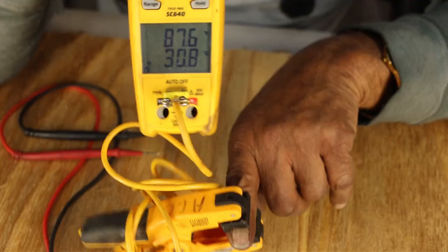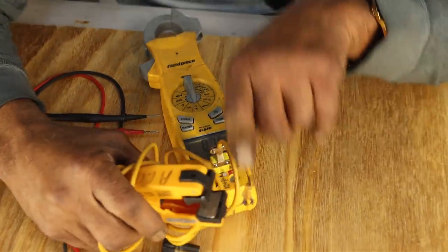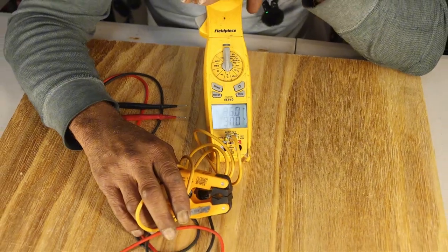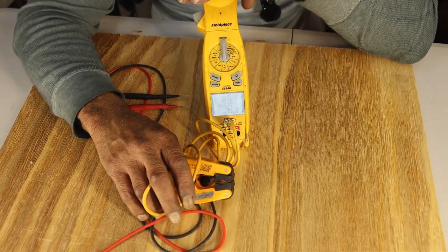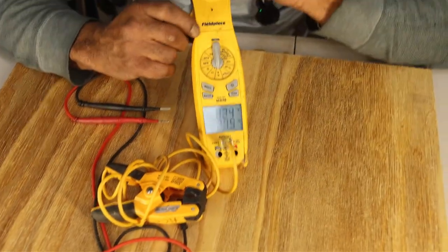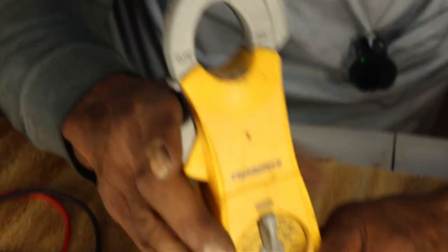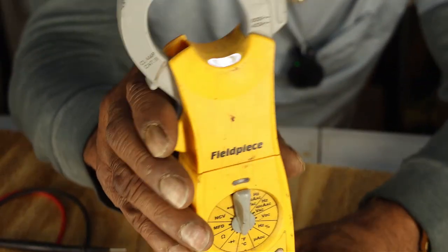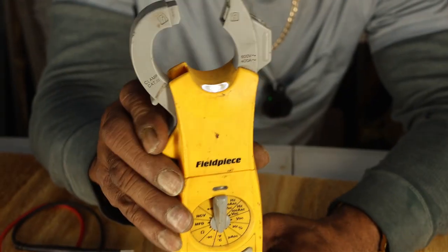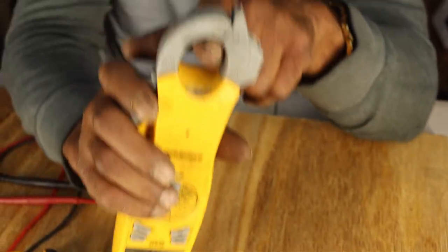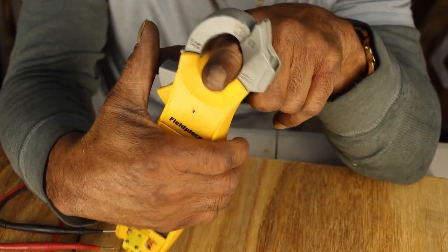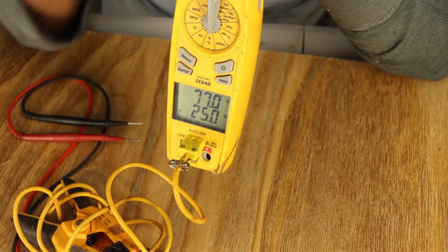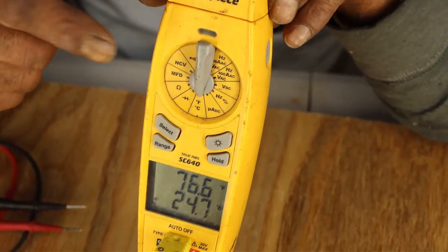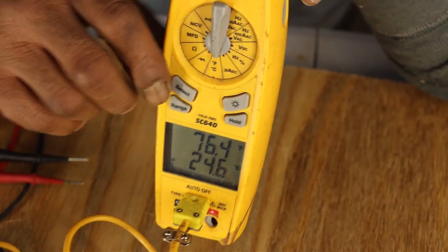Okay? Some of the different uses for our amp probe, our multimeter, our Fieldpiece. They are made by a multitude of different vendors. You can also use the top of it when you're checking the amps going to your compressor or the amps going to a motor. I just stick one wire in between here, clamp it on, and set it at amps, and it'll tell me the amps that a particular appliance is drawing at that time.